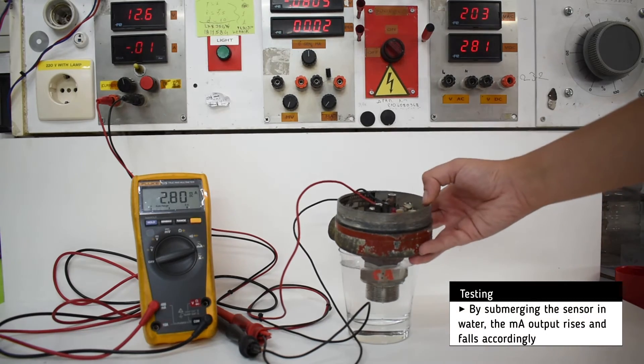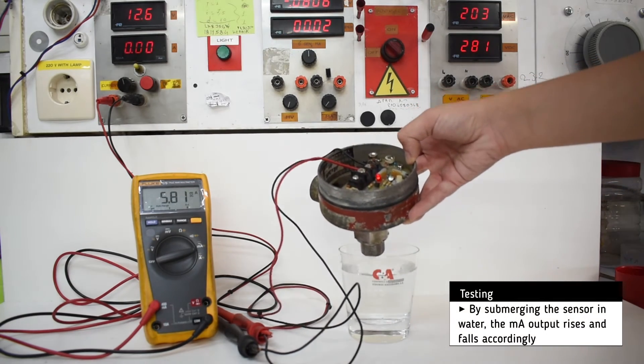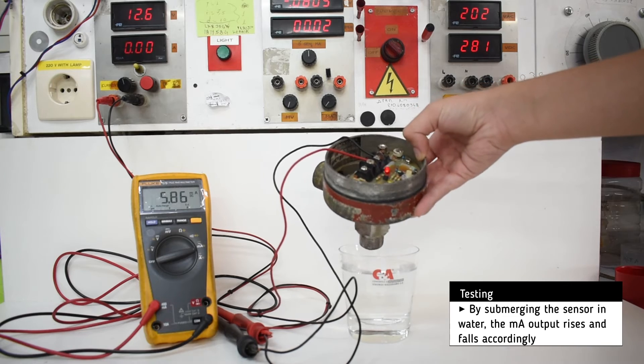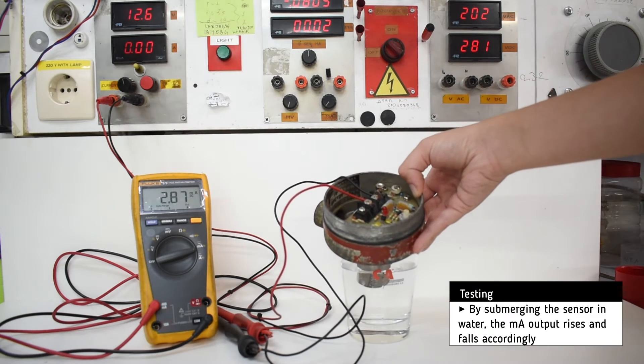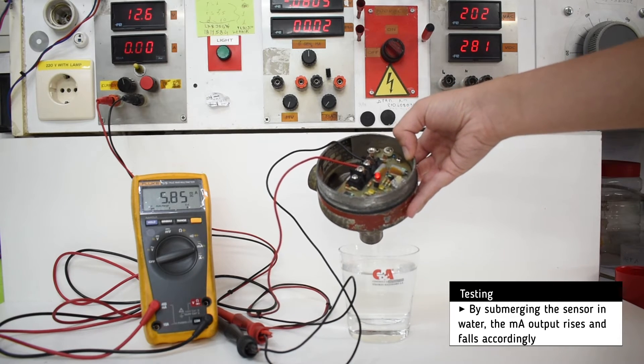By submerging the sensor in water, the milliamp output defaults to about 2.8 milliamps, and the LED indicator turns off.